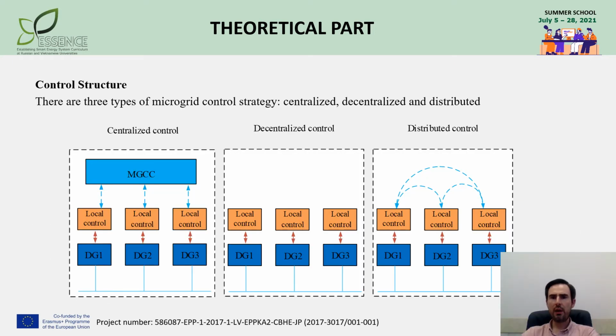To ensure reliable and economically efficient microgrid operation, an appropriate control system is always required. There are three possible control strategies. Centralized control is time-proven, fast and well-developed for large power systems, but its drawbacks are that there is a need to establish at least two communication channels, main and reserve, between each component and the controller, and the fact that if the centralized controller is lost, its functions cannot be implemented.